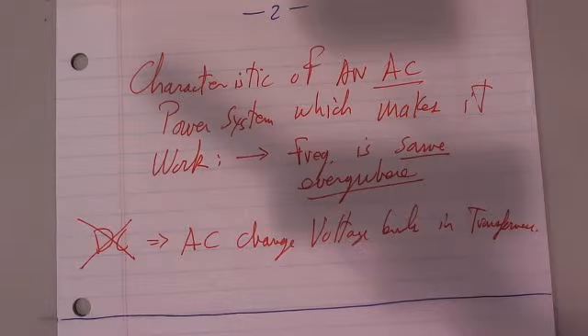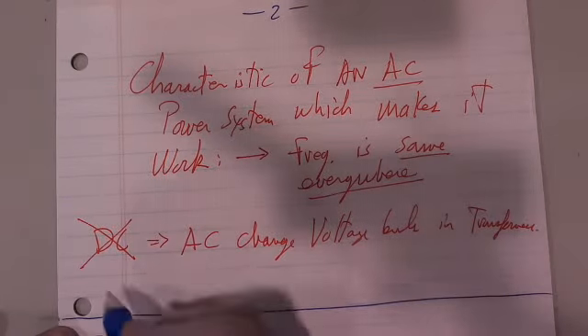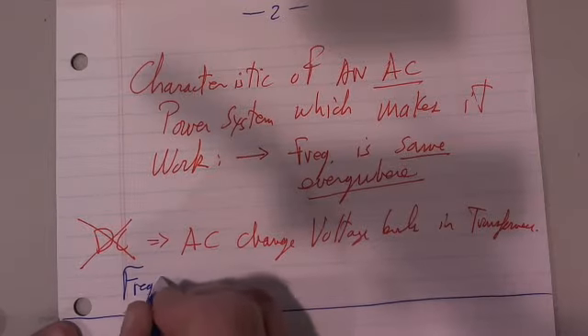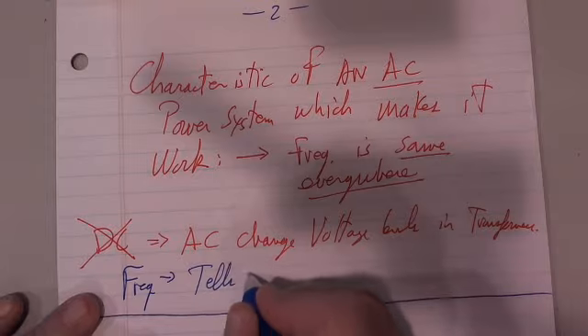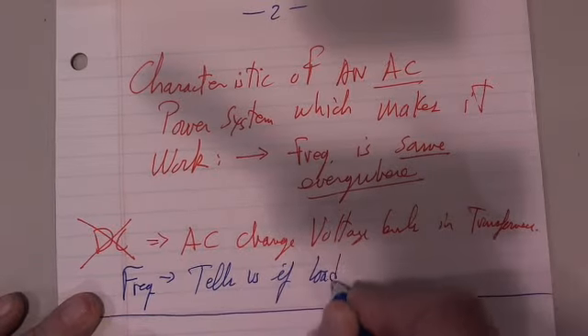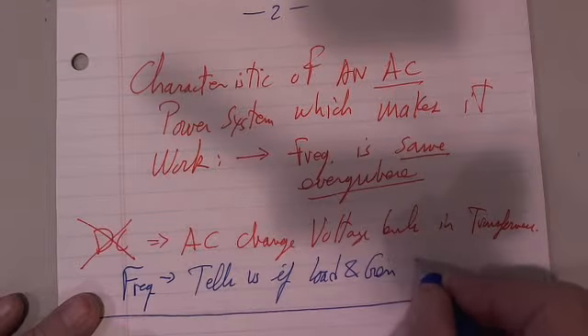But the other part of it that sort of came along for a great advantage is the frequency is a signal that I can look at, and it's the same. The signal stays the same everywhere. It's as if I ran a communications line to every control center and every generator all over the system to tell it what the load balance was. So once again, I'll put this in blue here. Frequency tells us if load and generation are balanced.